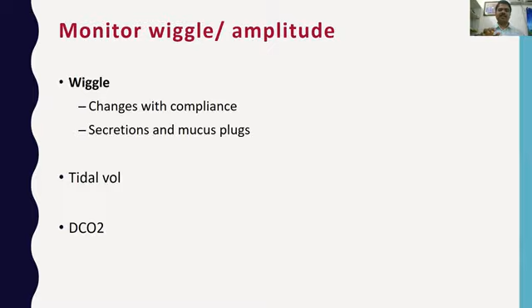So what is this DCO2, how to monitor it, and what is the clinical implication of this? DCO2 basically tells about the gas transport coefficient. So it basically tells about the CO2 diffusibility, otherwise called the CO2 diffusion coefficient. The formula for this is VT square into frequency. So VT square into frequency. So it is displayed on the ventilator.